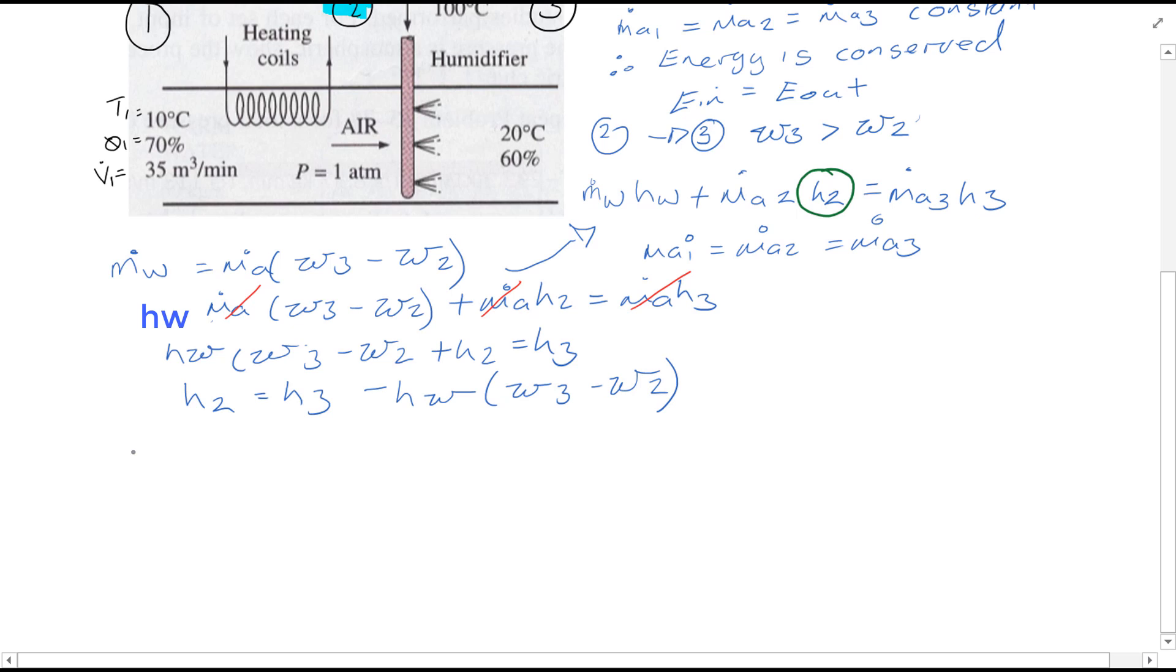So from the chart, we're given two values at state 3, so therefore it's possible to find H3, which is equal to 42.5 kilojoules per kg, and omega 2 is equal to omega 1, which is as we previously calculated by using the chart.